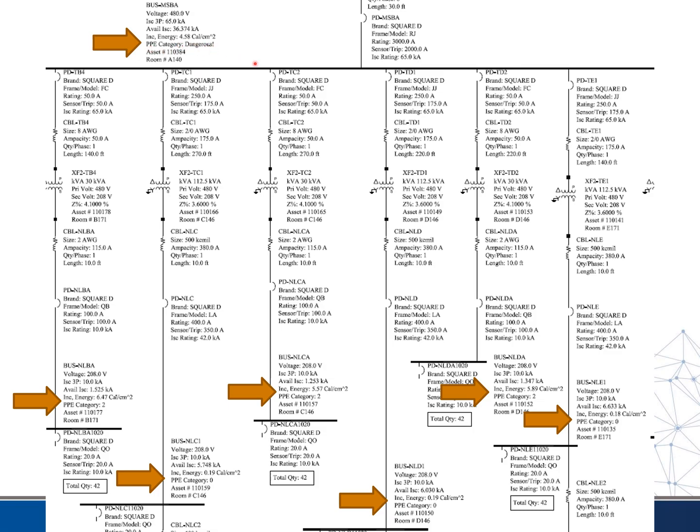In some cases you might have a PPE category called 'dangerous,' which means there isn't anything you can wear that's going to protect you. You'll find this a lot on the main switchboard or main transformer — there's just so much available energy there that the potential to arc is so great there's really nothing you can wear that will protect you adequately. That category means you really just can't work on this while it's energized — you're going to have to do an outage to work on that piece of equipment.